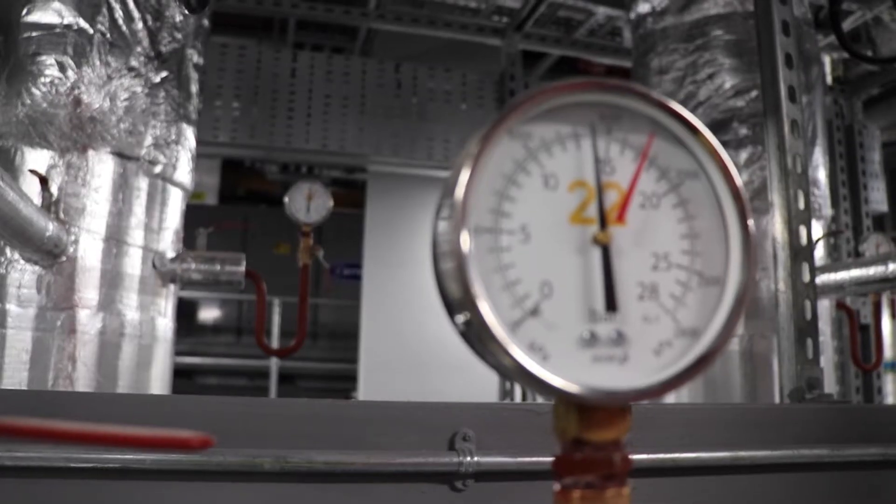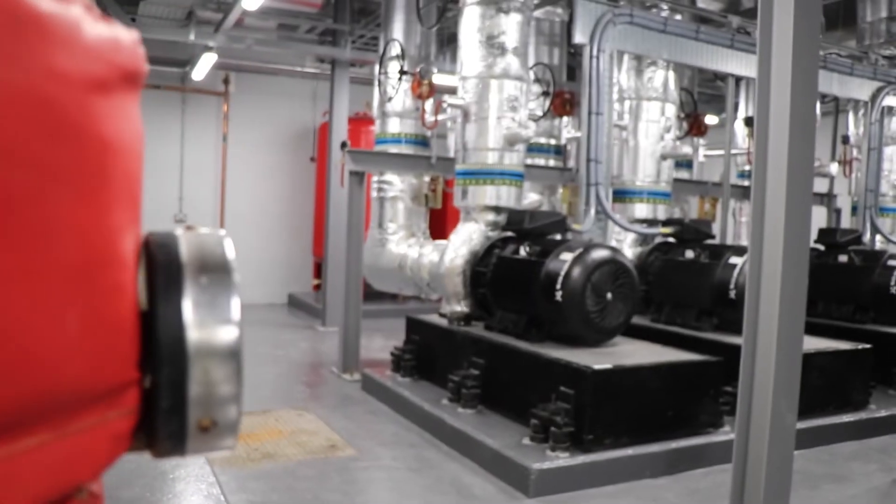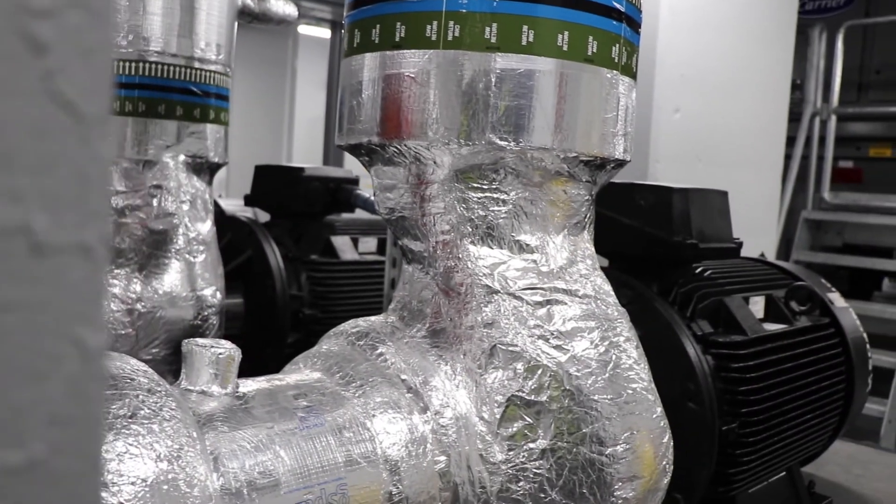Because of the height of the building, the pressure in all the hydraulic systems is larger than what you typically see. To overcome this, the designers separate the systems so there are express systems which distribute the heating, cooling, and condenser water throughout the building, and they operate at a higher pressure — up to 25 bar.